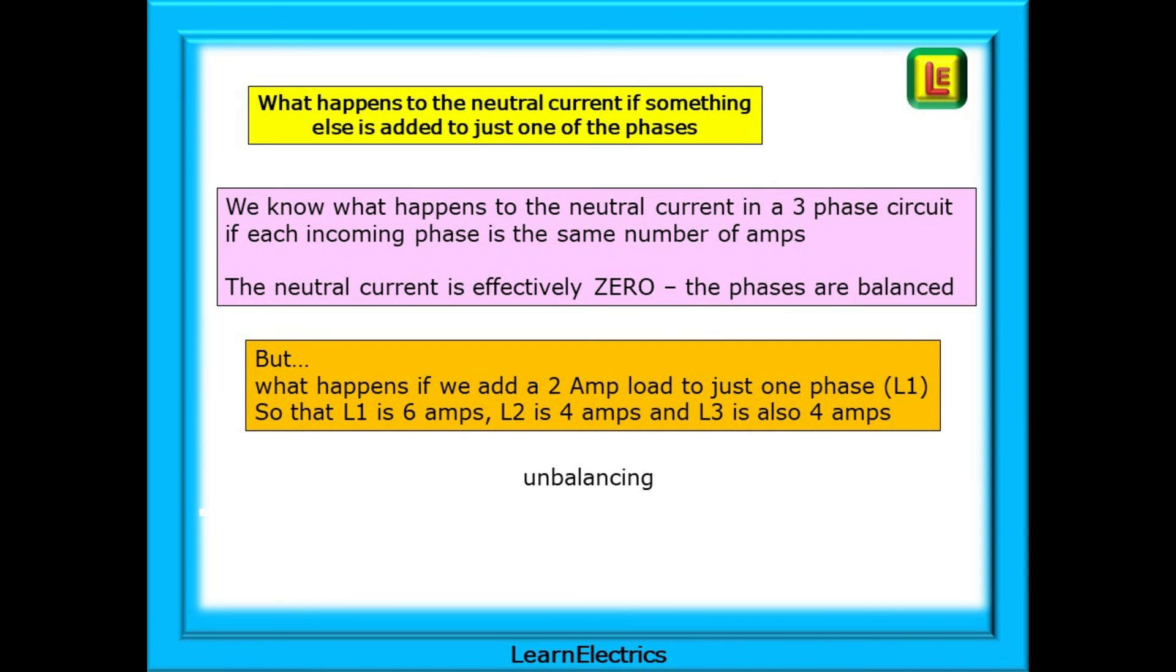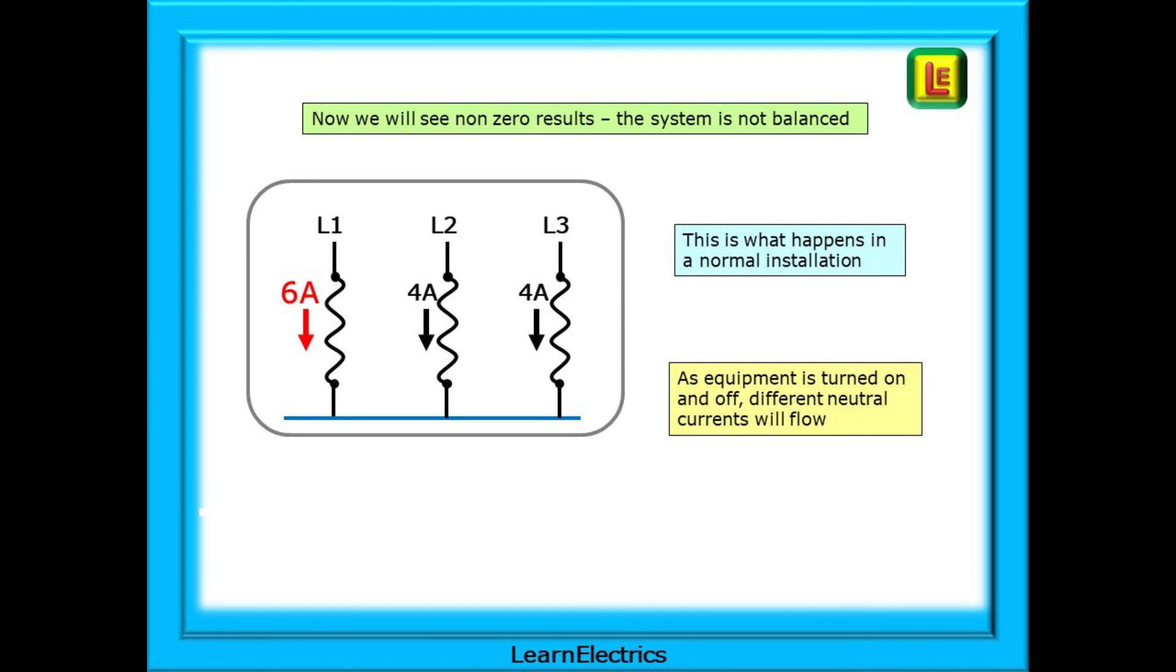But what happens to the neutral current if something else is added to just one of the phases? We know what happens to the neutral current in a three-phase circuit if each incoming phase is the same number of amps. The neutral current is effectively 0, and the phases are balanced. But what happens if we add an extra 2-amp load to just one phase? Let's say L1. So that L1 becomes 6 amps, L2 stays at 4 amps, and L3 is at 4 amps also. Now, we will start to see non-zero results, because the system is unbalanced. And this is exactly what happens in normal situations.